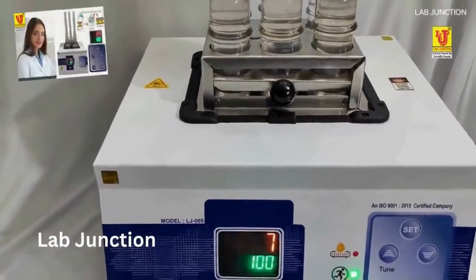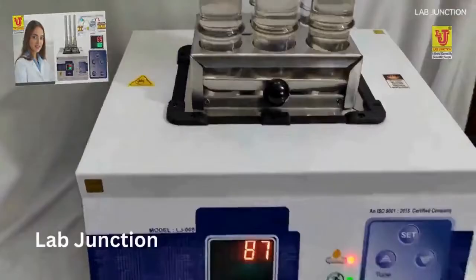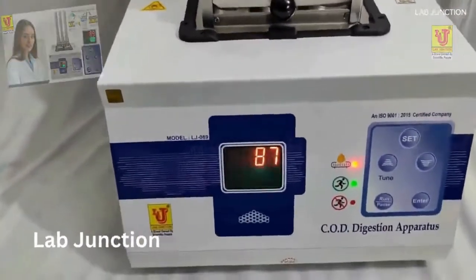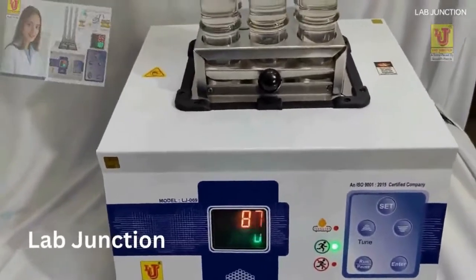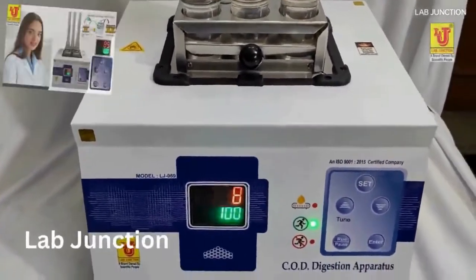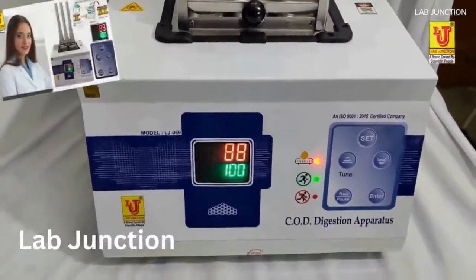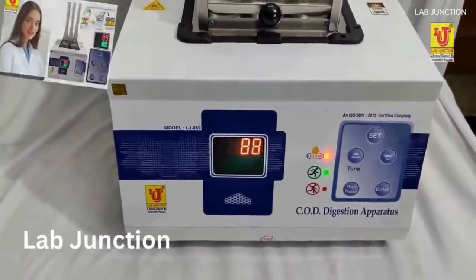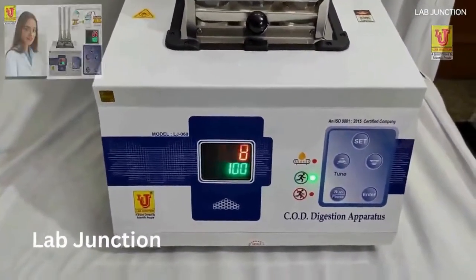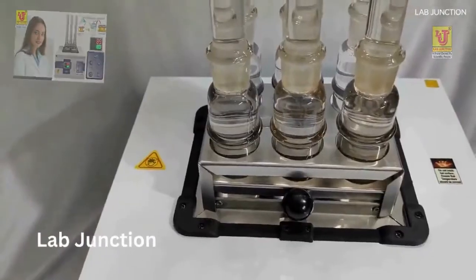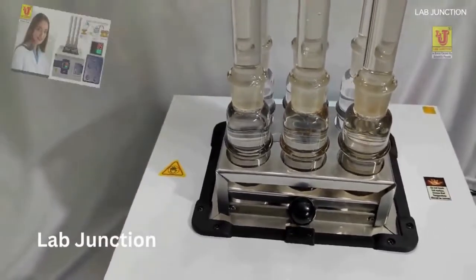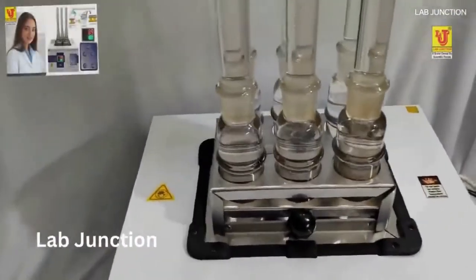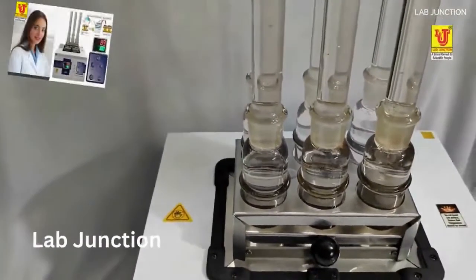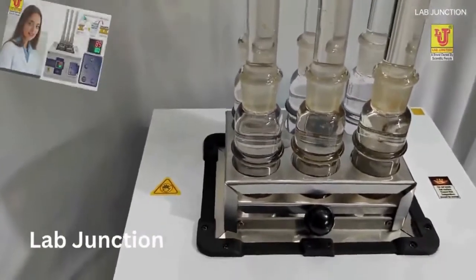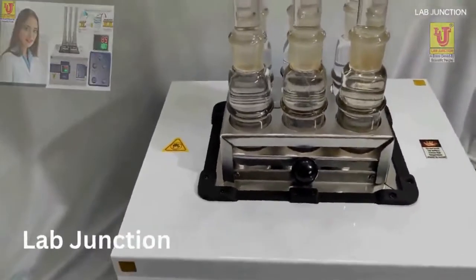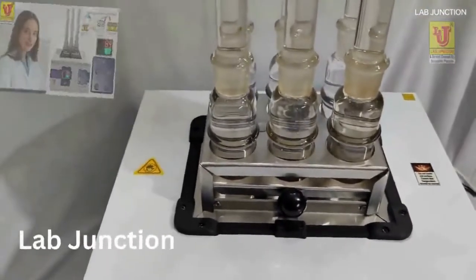Experiment starts. If you press pause key, your experiment stops. Always after feeding temperature or time, you have to press enter key. Then the instrument automatically saves your desired value of temperature and time. This instrument is supplied in two wooden boxes. One wooden box is for the instrument and one box is for test tubes and digestion block stand.